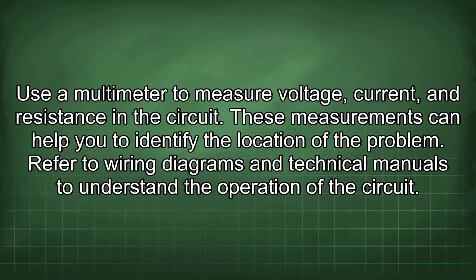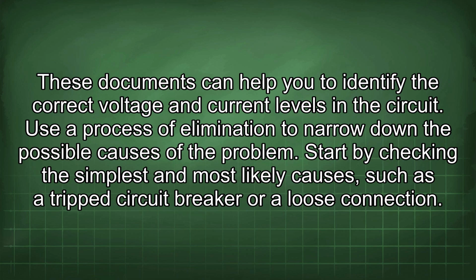Use a multimeter to measure voltage, current, and resistance in the circuit. These measurements can help you to identify the location of the problem. Refer to wiring diagrams and technical manuals to understand the operation of the circuit. These documents can help you to identify the correct voltage and current levels in the circuit. Use a process of elimination to narrow down the possible causes of the problem. Start by checking the simplest and most likely causes, such as a tripped circuit breaker or a loose connection.